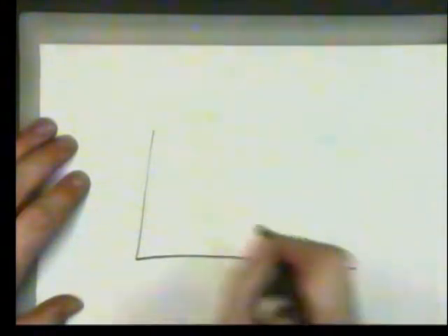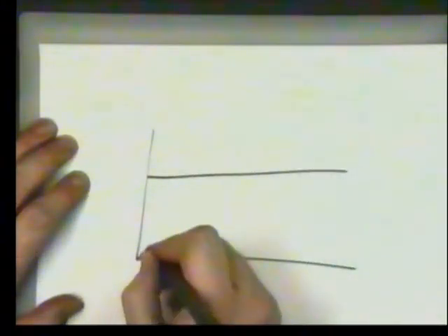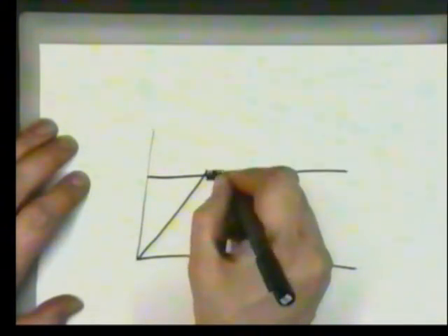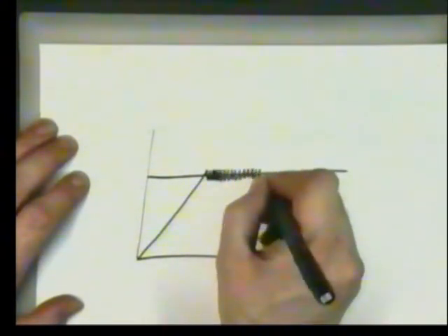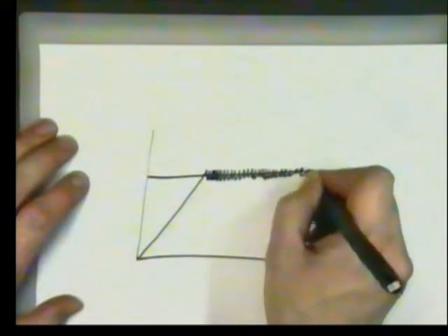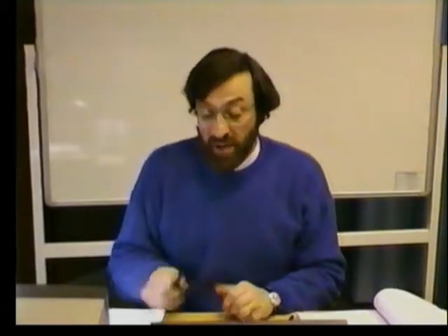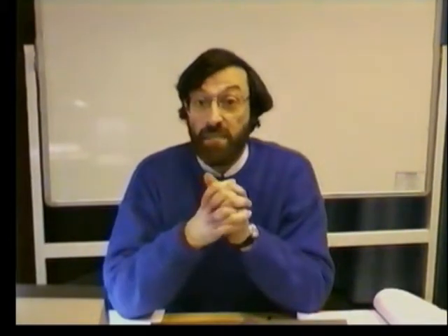If here's our set point, we'll rise up to it, we'll immediately realise what happened, and we will get some very, very high frequency oscillations around the set point, extremely high speed. And that certainly will happen if you've got something that is very fast, very good. Actually, the better the processor, the more chance of this happening.